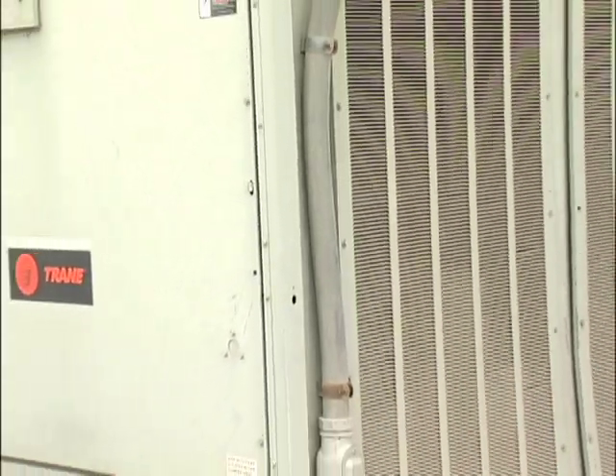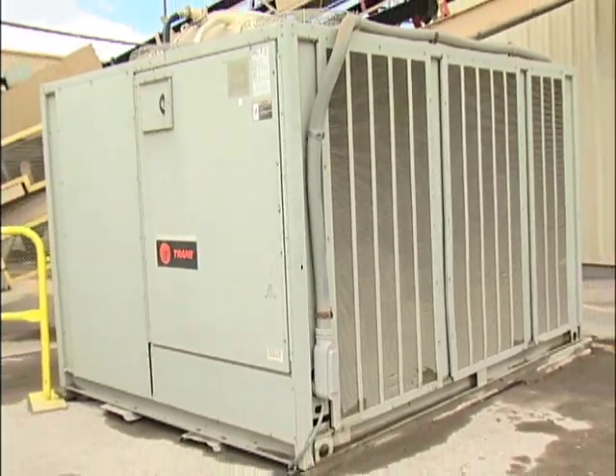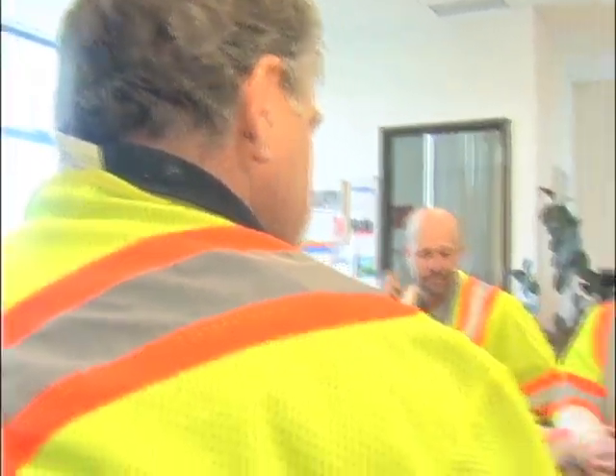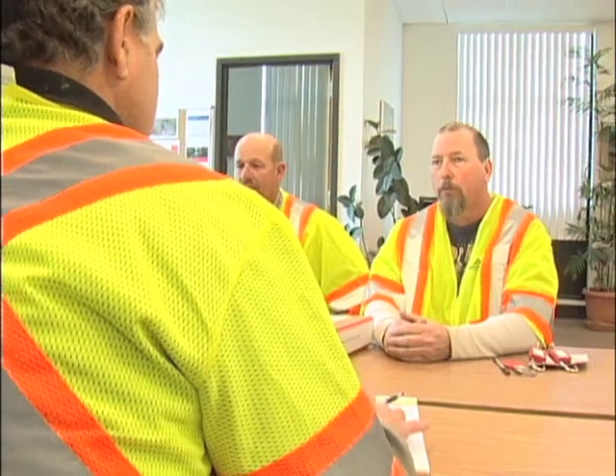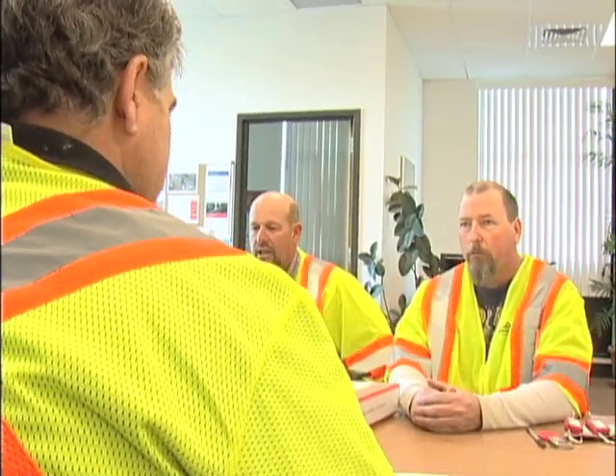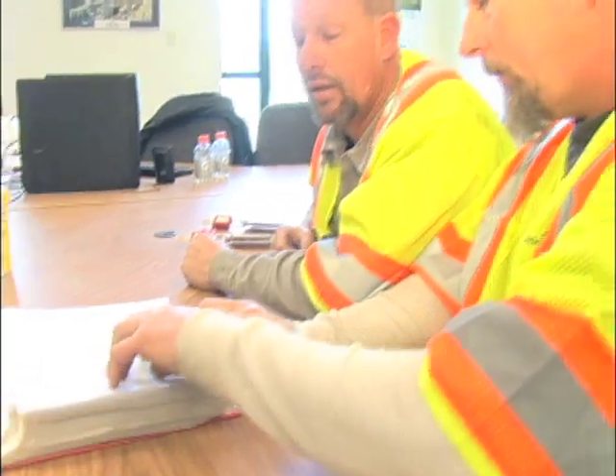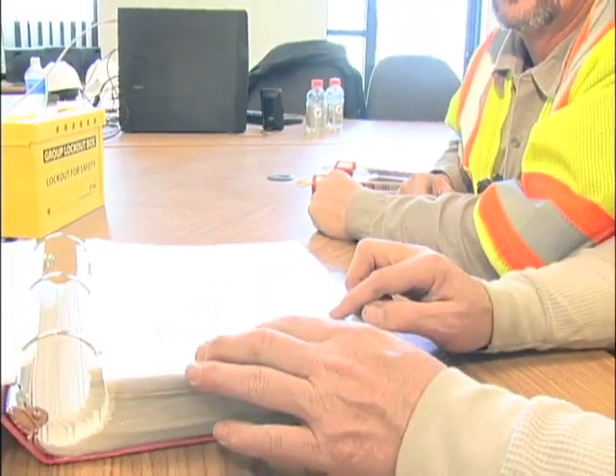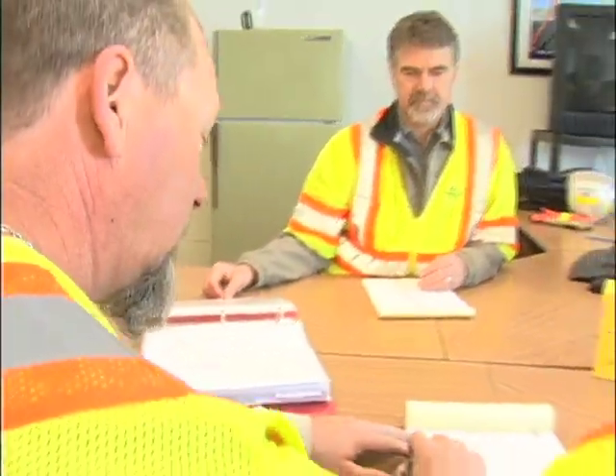Okay, guys, how many lockout points do we have for this piece of equipment? There's two. The electrical disconnect and the water valve. Number 1. Preparation by authorized employees for shutdown is step 1. This includes identifying how many sources of energy and what kinds of energy must be locked out and tagged out. It also includes describing in order all steps of equipment service, maintenance, repair, replacement, and/or installation. It must include steps for reversal of lockout, tagout, and tryout procedures.